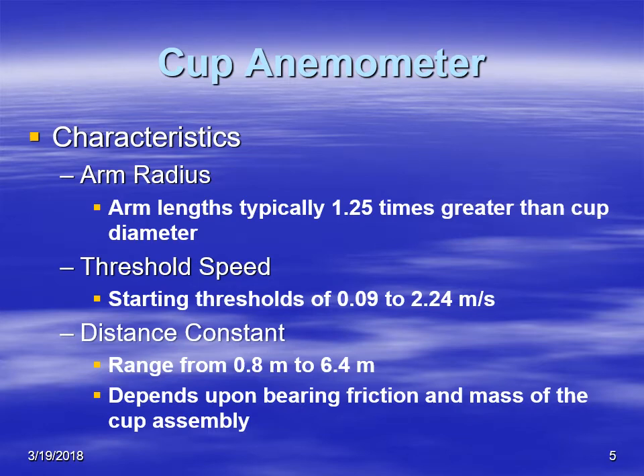As far as the characteristics of the cup anemometer, the arm radius typically is about 1.5 times the cup diameter. Also, threshold speeds are on the order of 1 to 2 meters per second, and then distance constants anywhere from a little bit below 1 meter to somewhere above 6 meters, but definitely less than 10 meters. So of course we talked about distance constants and threshold wind speeds before. We said that it all depends upon the inertia of the wheel. Also, it depends upon the bearing friction, and as you have bigger and bigger cup wheels, you add more mass to the assembly, and of course mass is one of the big factors in determining the distance constant.